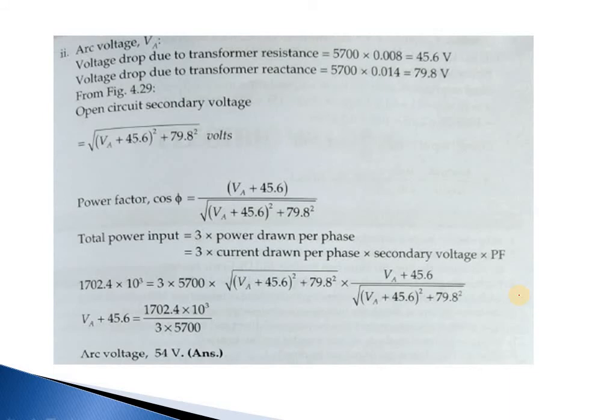Now for calculating the power factor, it will be (VA plus 45.6) divided by the square root of (VA plus 45.6) whole square plus 79.8 square. Total power input equals 3 into power drawn per phase, equals 3 into current drawn per phase into secondary voltage into power factor. So putting all these values, we get the value of VA at arc voltage, that is 64 volts. We have calculated that the arc voltage value is 64 volts.